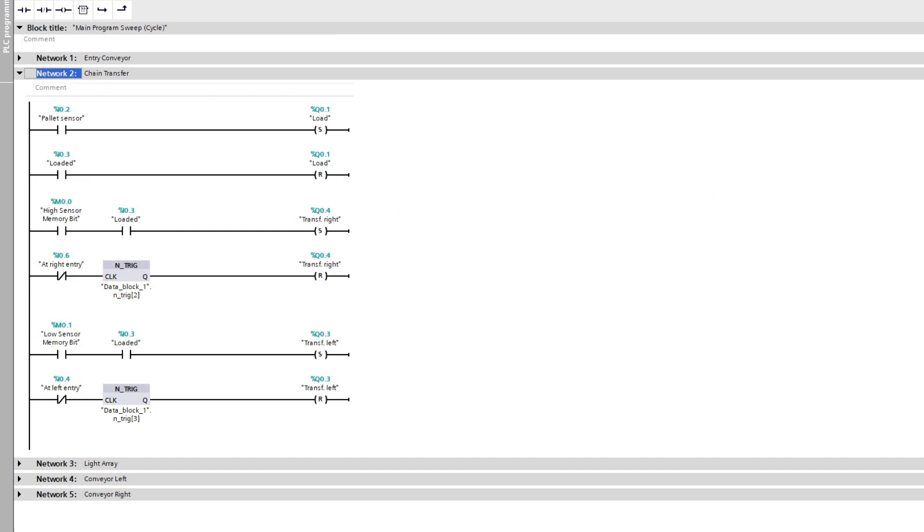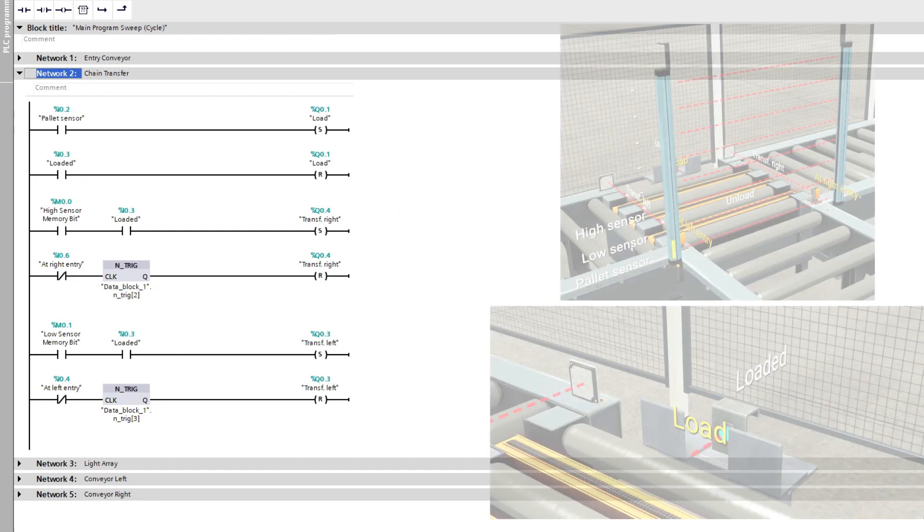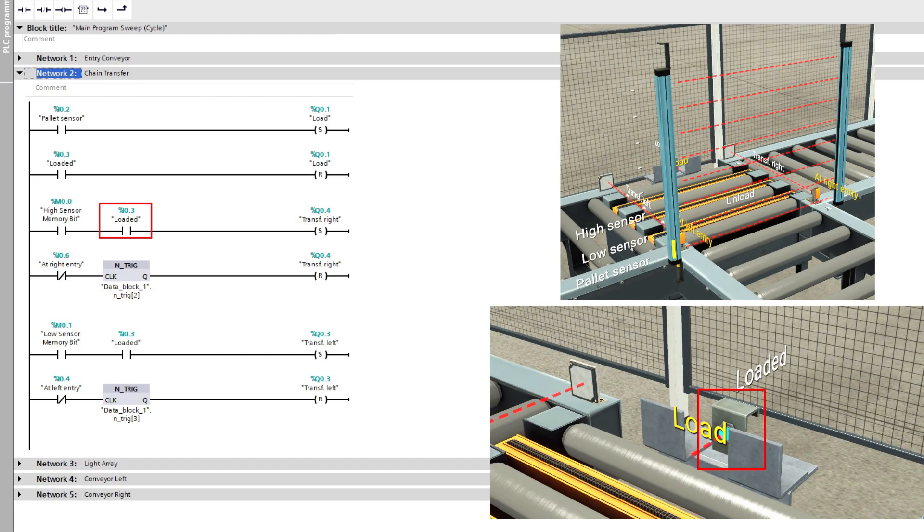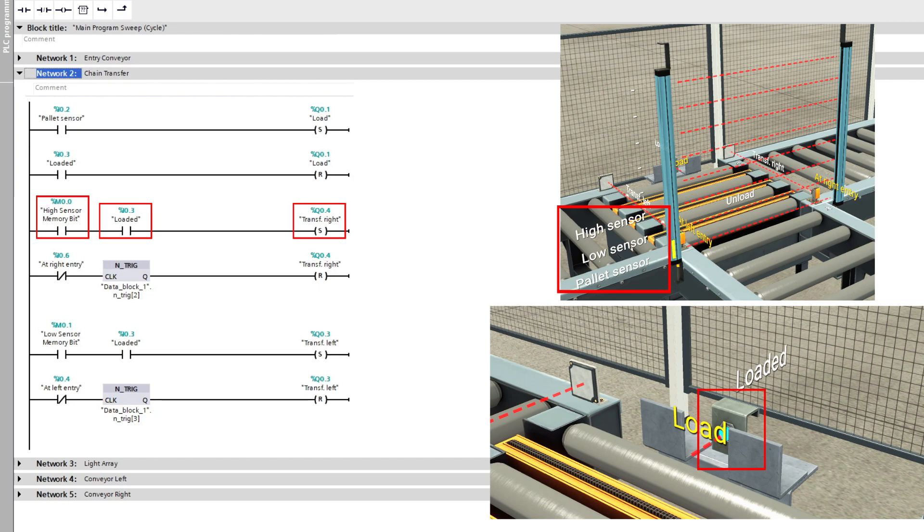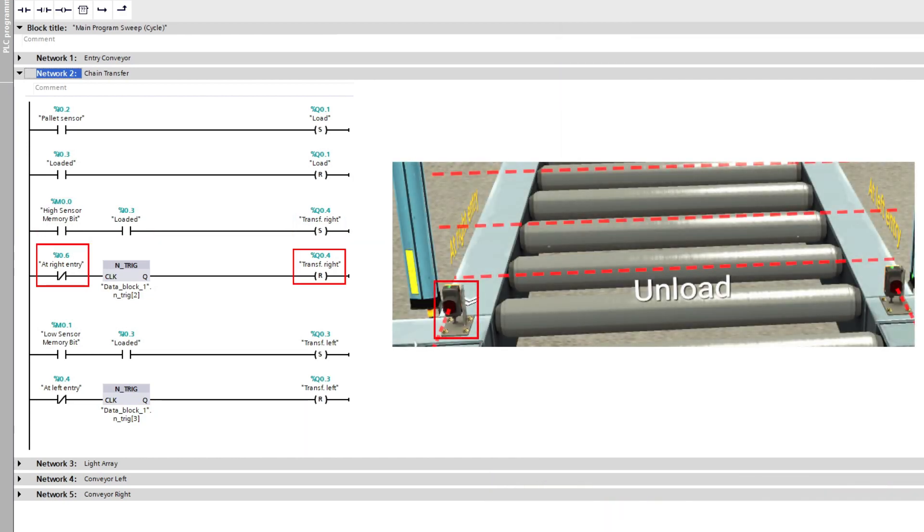To make the pallet transfer right, we need the loaded sensor to be true and get a signal from the light barrier if it is a big or small box, in this case a big box. And once the pallet has passed by the at right entry sensor, it will reset itself.